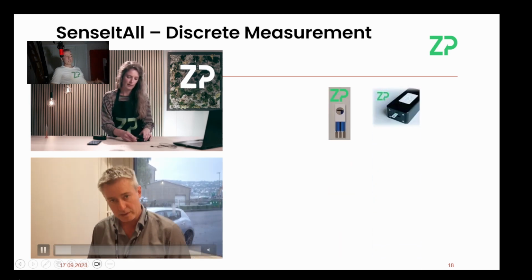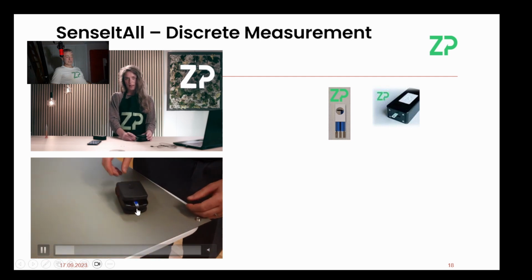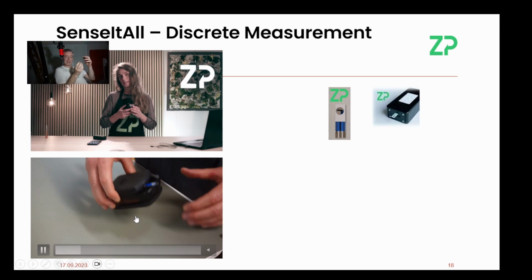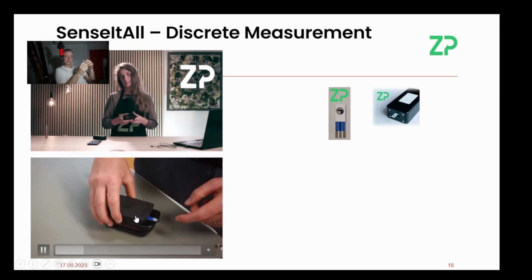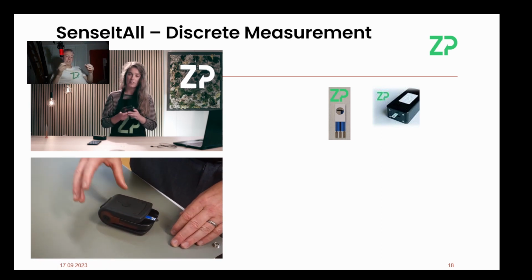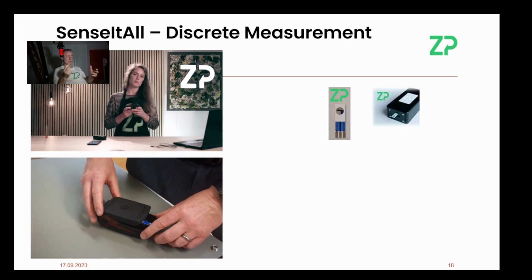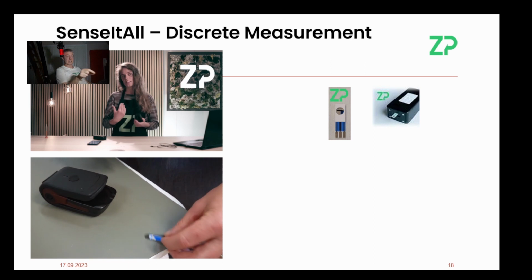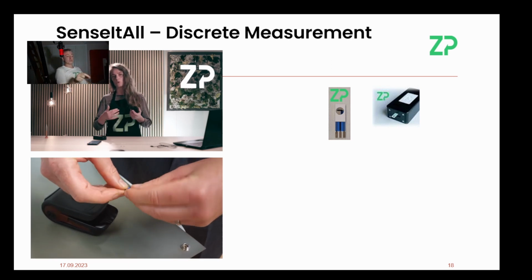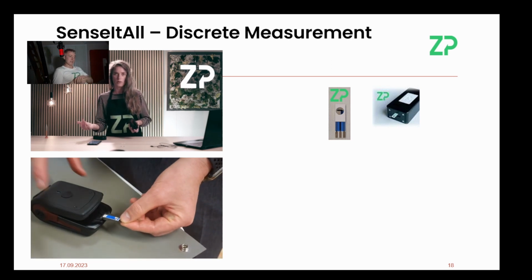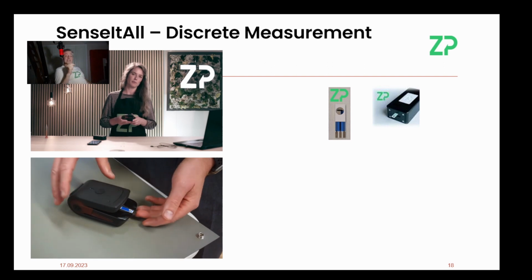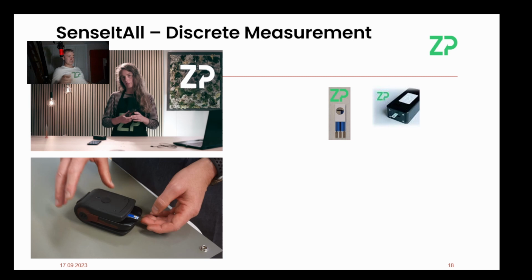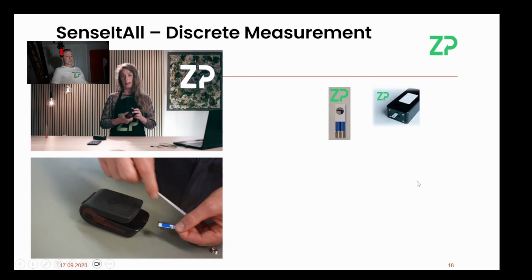We have hardware, but the hardware has got a lot more elegant these days. In fact, there's the hardware now. You can see my hand upon that. Really quite nice. It clicks in, it clicks out. And that's really important because at the moment people are using instruments where they're slotting this thing into the front. And by the way, those slotting connections soon wear out. Also it's very easy to get liquid into the connections, so that's an absolute disaster. So this one, you'll just see it clicks around really elegantly.